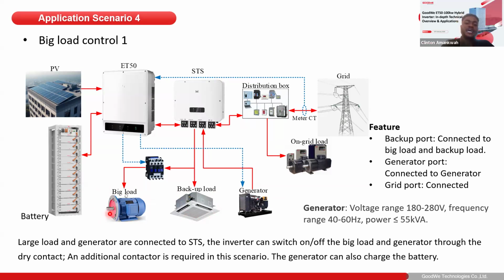How do we achieve this? That is where we make use of the GoodWe ET 40, 50, 100 kilowatt inverter signal load control. With the introduction of an external contactor, the inverter can send a signal to this contactor to tell it to open or close its relay, allowing power to flow from the backup port of the STS to this big load, depending on the battery SOC.